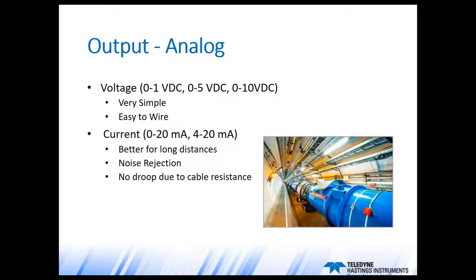For analog output, there are two broad categories: voltage and current. Voltage output can often be linear, with the output directly proportional to pressure — zero to one, zero to five, or zero to ten volts DC — and these are generally easy to wire up. Current outputs like 4–20 milliamp are nice because they allow connection over very long distances without losing voltage signal, and they are also less susceptible to electrical noise. There are different classifications of 4–20 milliamp: sensors can be active (sourcing current) or passive (sinking), and loops can be isolated or non-isolated, so ensure your vacuum gauge is compatible.